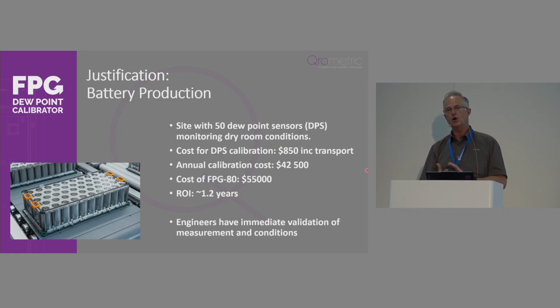So the annual cost for this particular one battery production customer was $42,500 per year for calibrating their dew point sensors. The cost of the FPG was around $55,000 US, so the return on the investment was just over 1 year, which is pretty good justification for investing in an instrument for calibration.